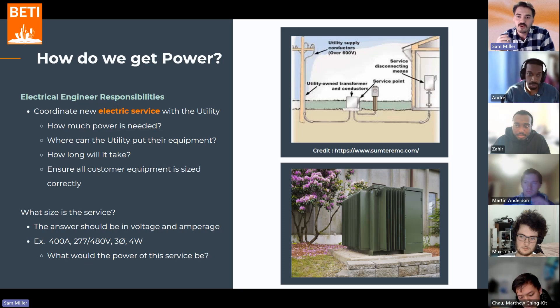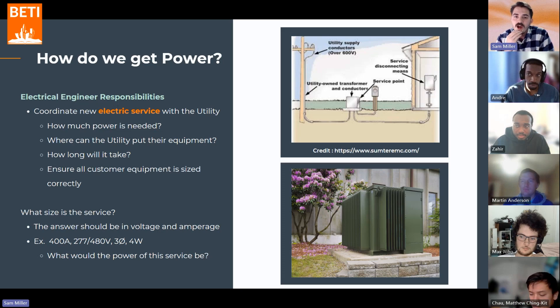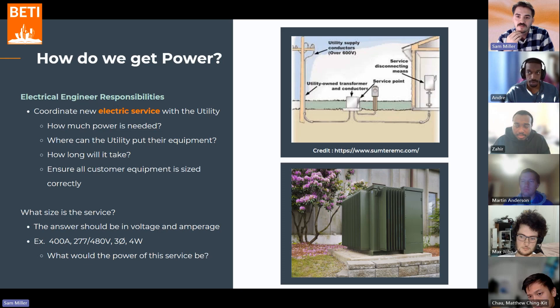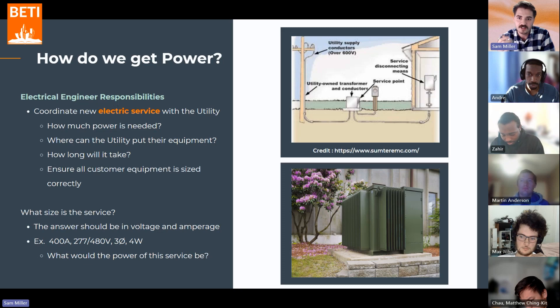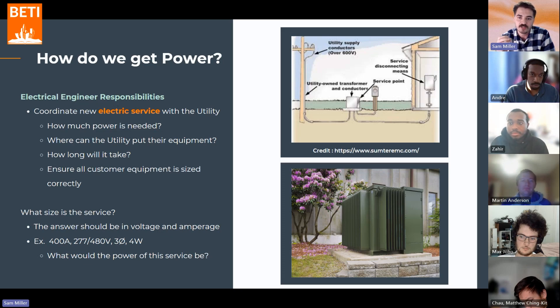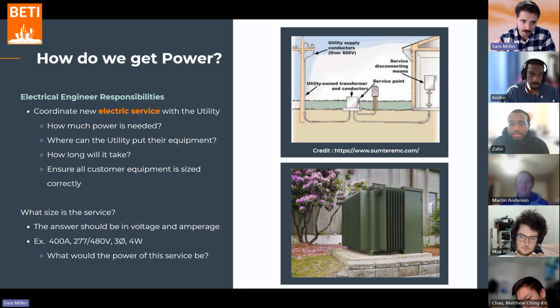For example, I might have a project where I know they want to pull in a hundred new electric vehicle chargers to a site. I've got to figure out how much each of those electric vehicle chargers draws, add them all up, do my calculations, and go back to the utility and say, we need a new service — it needs to be this many amps, this many volts, and we need a new transformer. And I need to work with you on where to put that on the site.